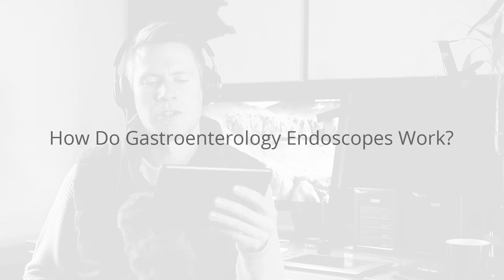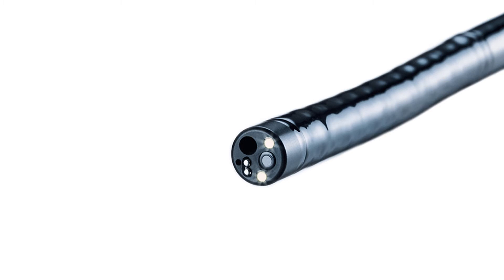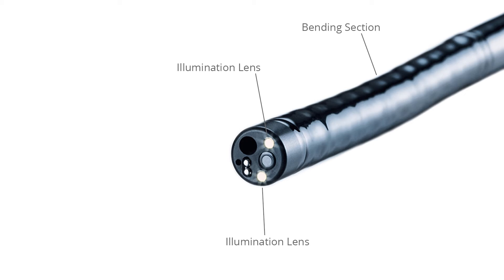The distal end is inserted into the GI tract and the user operates the controls on the proximal end. Typical components at the distal end include the bending section, which can be articulated vertically and horizontally to navigate through the GI tract. The illumination lens transmits light via fiber optics. This light is reflected and returned through the objective lens to form the image. Fiber endoscopes transmit this light through fiber optics, whereas video endoscopes capture the light using an imaging sensor within the distal tip.